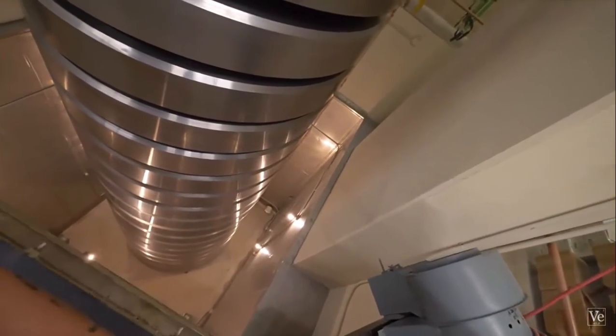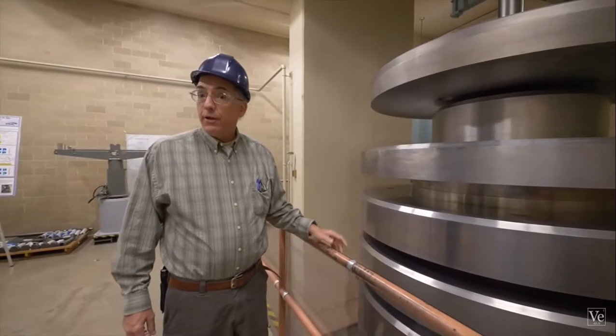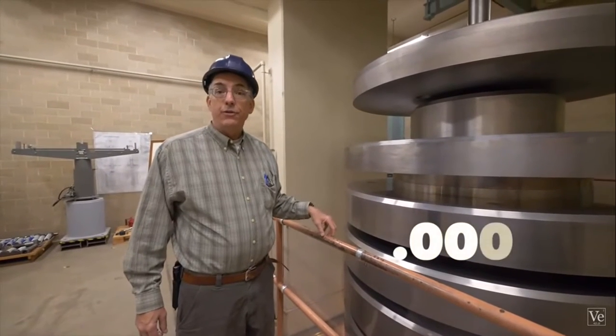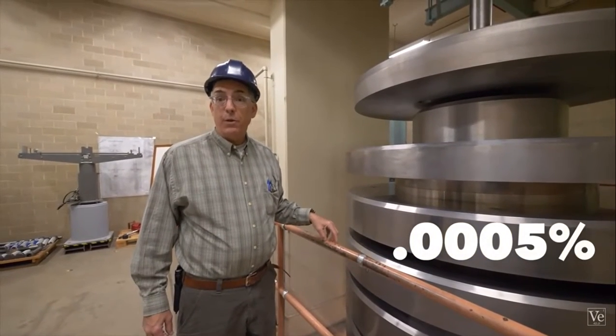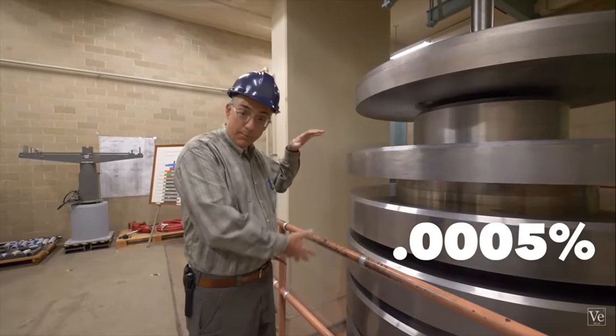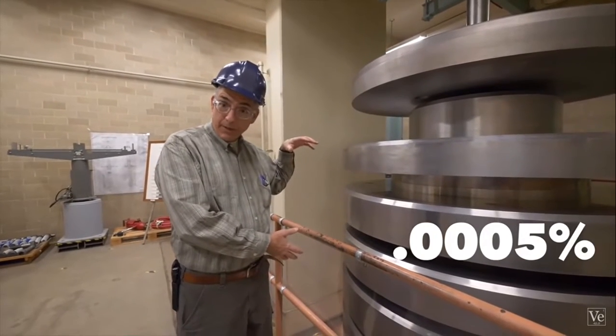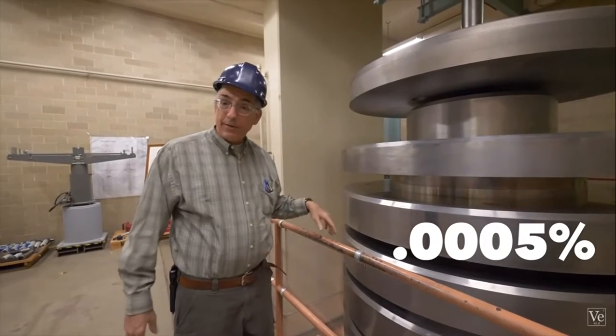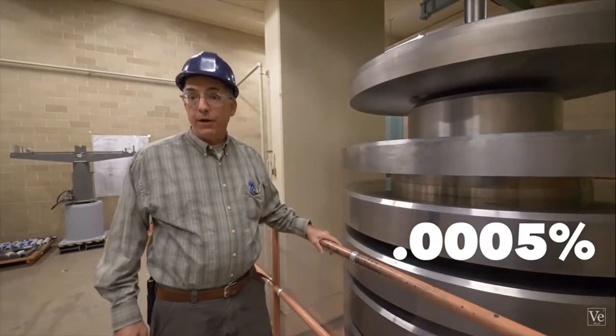And we have to have that because what we sell is the vertical force vector that's generated by these weights hanging in the gravitational field. We sell that with an uncertainty attached to it of 0.0005%, 5 parts per million, so that means at full 1 million pounds of applied force, we guarantee that to be accurate, if you will, within 5 pounds.